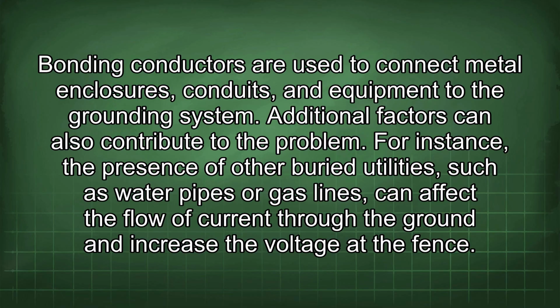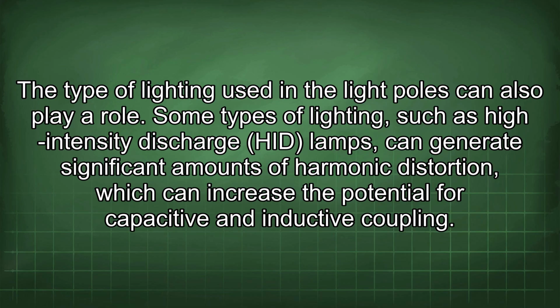Additional factors can also contribute to the problem. For instance, the presence of other buried utilities, such as water pipes or gas lines, can affect the flow of current through the ground and increase the voltage at the fence. The type of lighting used in the light poles can also play a role. Some types of lighting, such as high-intensity discharge (HID) lamps, can generate significant amounts of harmonic distortion, which can increase the potential for capacitive and inductive coupling.